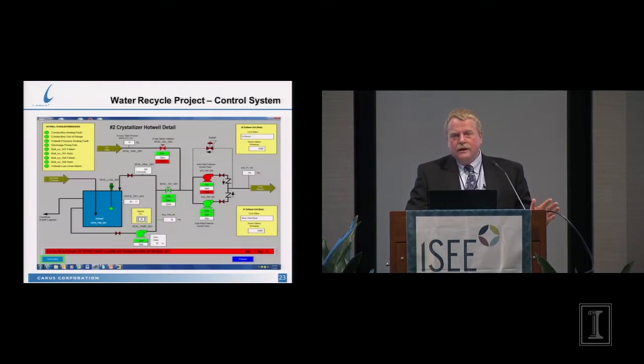I told you we do a lot of work on controls. This is the screen the operators actually use to control the plant. You can see that pump on the bottom, it's green, meaning it's running. We've got a VFD on it because we want to control the pressure coming out of it. We measure the crystallizer weir box temperature, and we also measure the conductivity.